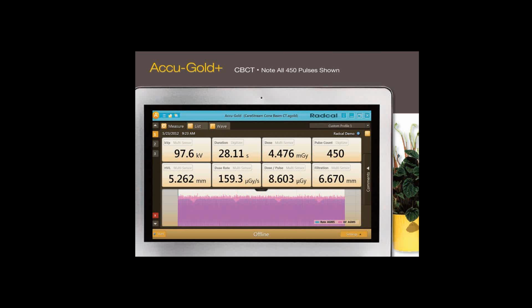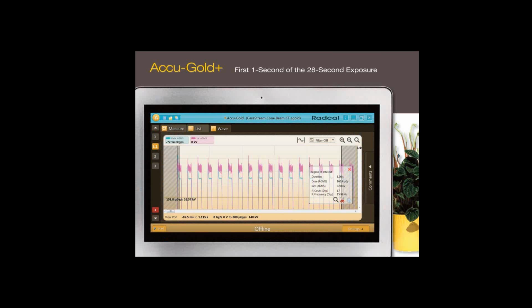To demonstrate the waveform capture capabilities, I've shown here a cone beam CT exposure that's 28.11 seconds long with 450 pulses. Accu-Gold+ captured the entire exposure and waveform, as you can see here. Capturing the entire waveform allows for a much more accurate and precise measurement as opposed to a small window of an exposure. And just to prove that that wasn't any noise, we can select waveform from the measure page to show the entire waveform for further analysis.